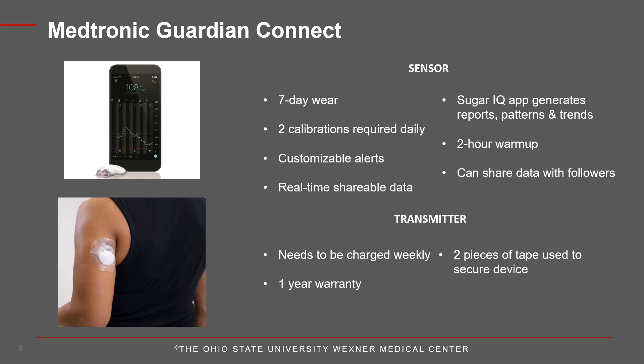The transmitter is reusable for up to 1 year, but does require a 10 to 20 minute charge in between sensor changes each week. The system requires a calibration from the user, a minimum of once every 12 hours. Data can be shared with up to 5 people. The Sugar IQ Diabetes Assistant app works with the Guardian Connect and can help the user identify patterns and understand trends. The transmitter that is used for this Medtronic standalone CGM is different than the transmitter that is used for the CGM that connects with the Medtronic pump.